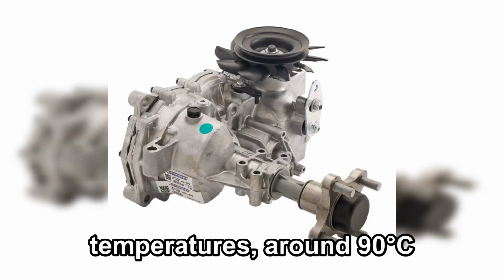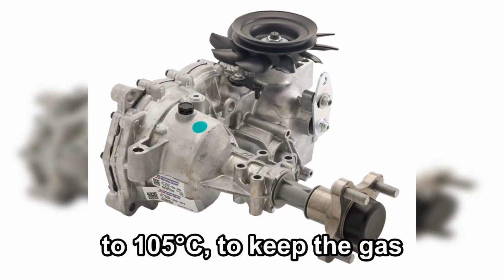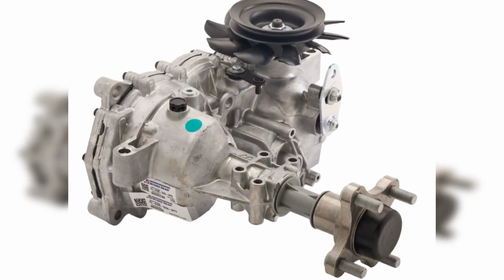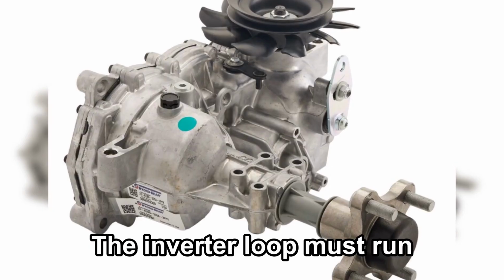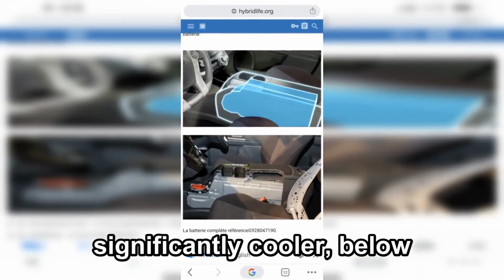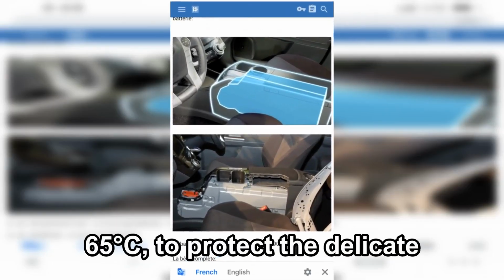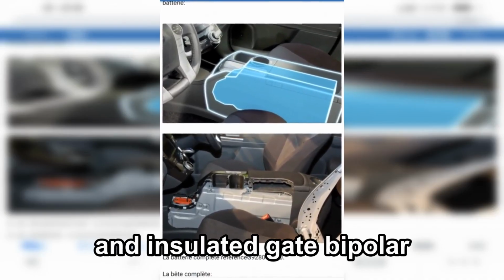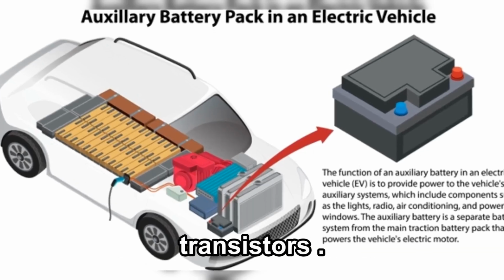The engine loop runs at high temperatures, around 90 to 105 degrees Celsius, to keep the gas engine operating efficiently. The inverter loop must run significantly cooler, below 65 degrees Celsius, to protect the delicate silicon-controlled rectifiers and insulated gate bipolar transistors, IGBTs.